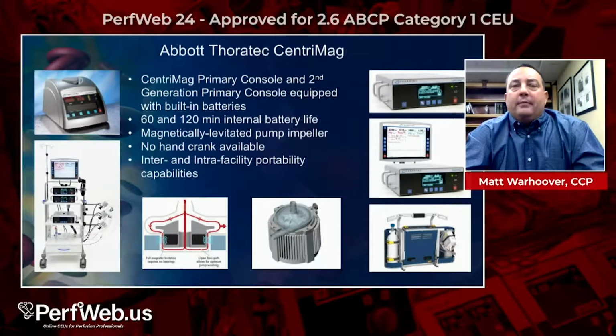And as far as from an ECMO standpoint, what I don't like about this is that there is no backup hand crank available. So when you're transporting, you always have to have two consoles with you, because if a primary console goes bad, whatever the malfunction is, electrical, mechanical, with it in that console, there's nothing you can do other than to change the console out. The lower left-hand corner shows you've got the two primary consoles up top. You've got a backup down below for that's more or less a BIVAD situation.